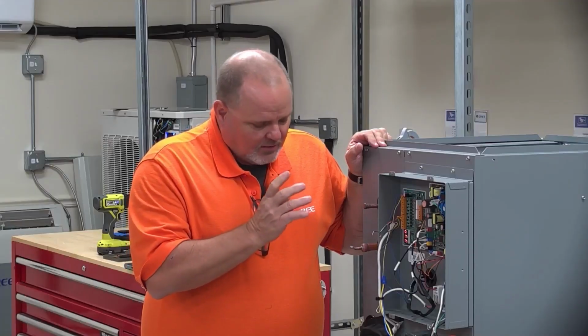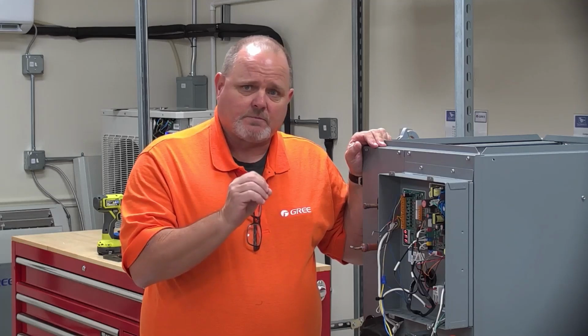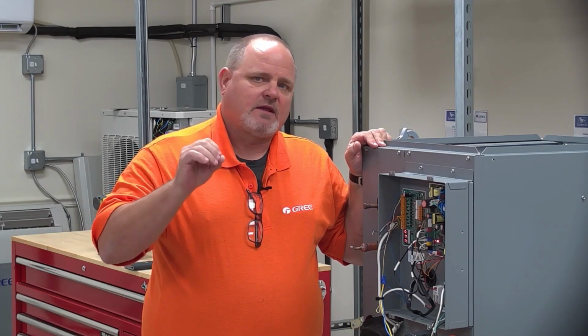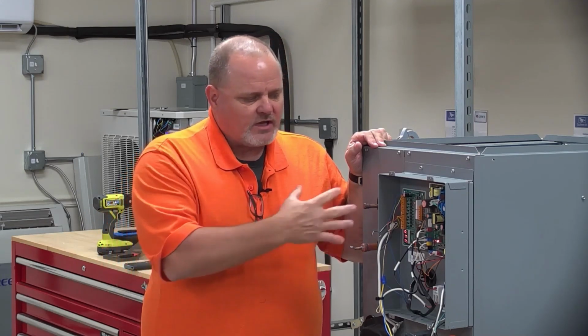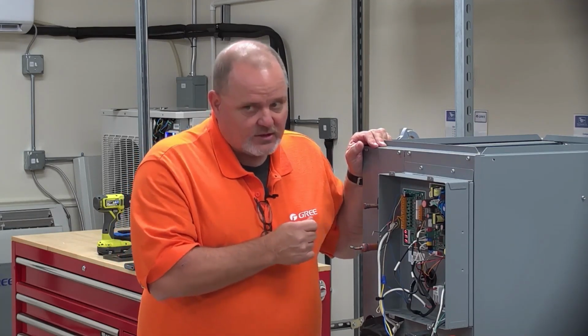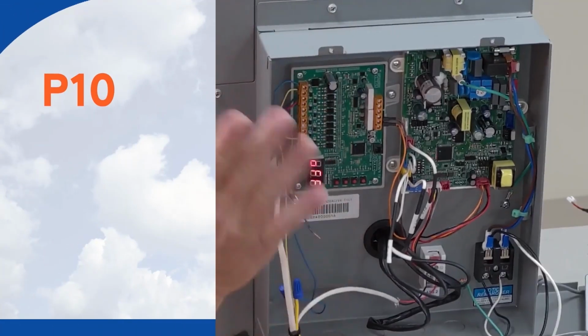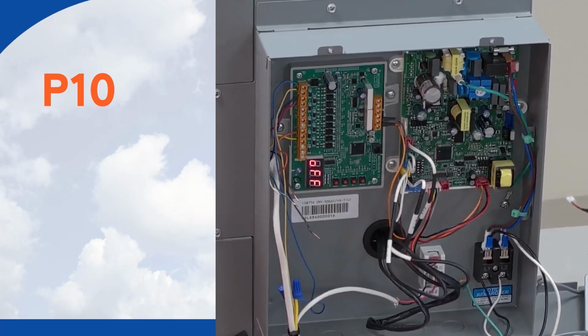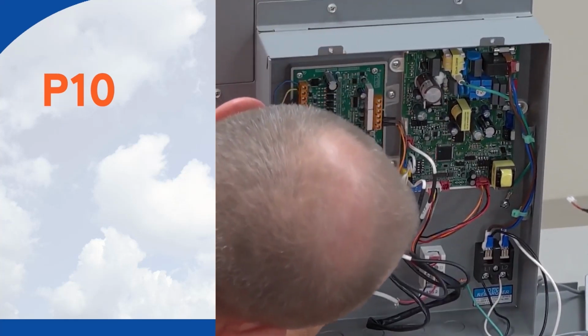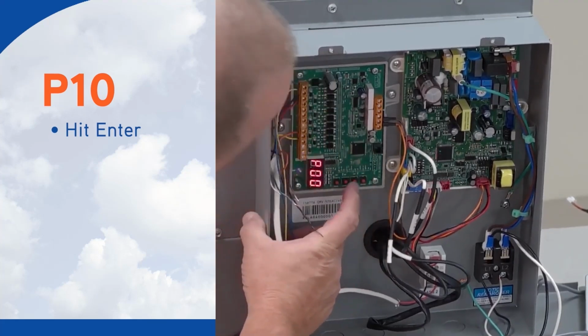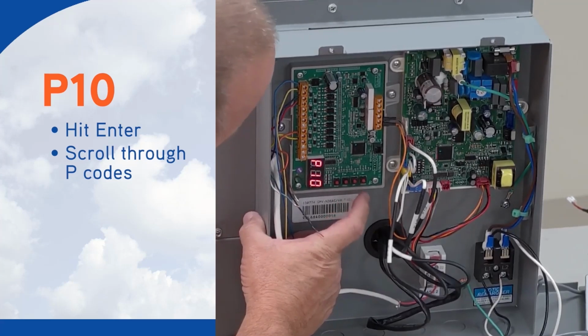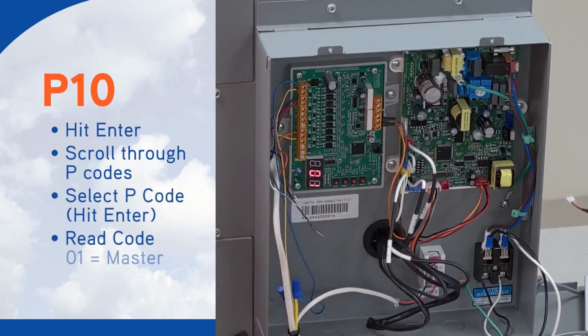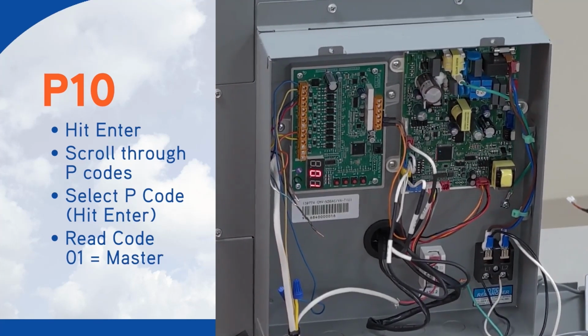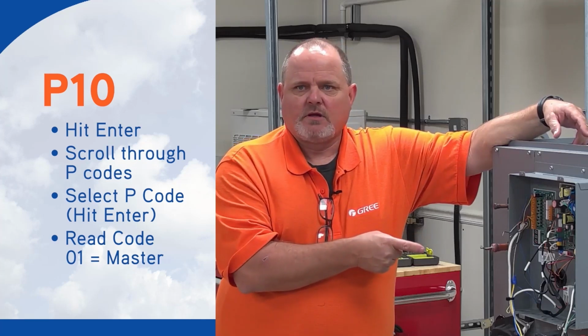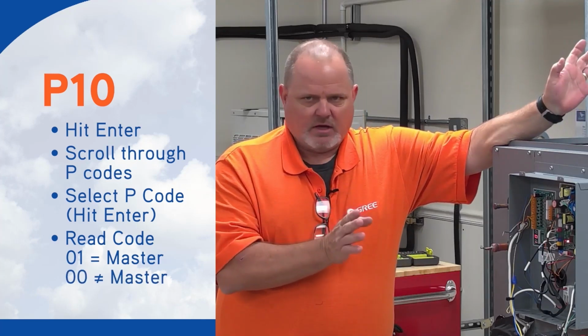Anyway, the biggest thing you got to know, like any other MultiPRO system, is that one of those indoor units is going to be dedicated to master. So when you set this up, do you want this to be the master? And the way you do that is the P10 code. This will be in the manual, so I don't expect you to memorize all this. But in the P10 code, if I just go in here and hit enter, and then I can scroll through the P codes. There's P10, I hit enter again, it's set for 01. Meaning, the minute I power this up, this becomes the master. If it's 00, it's not going to become the master.